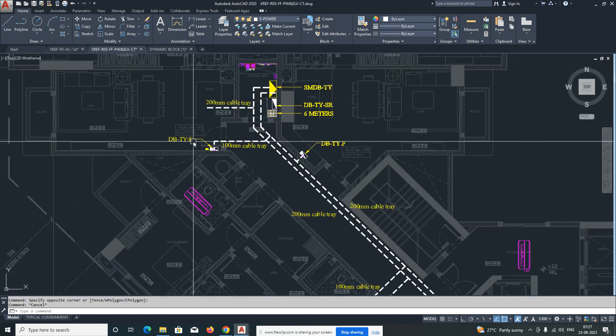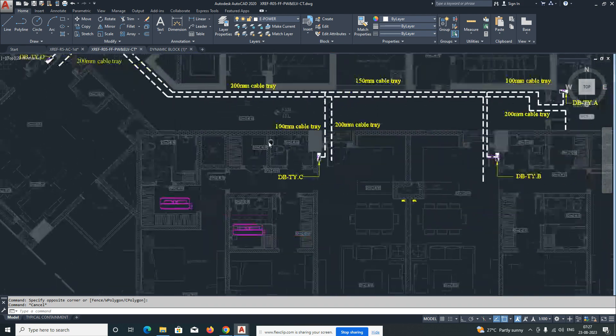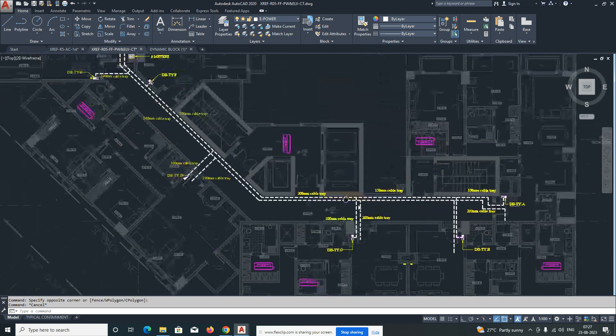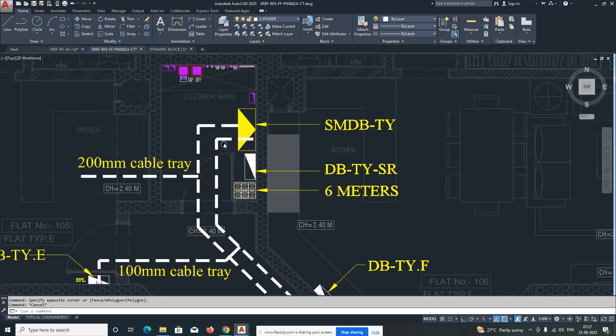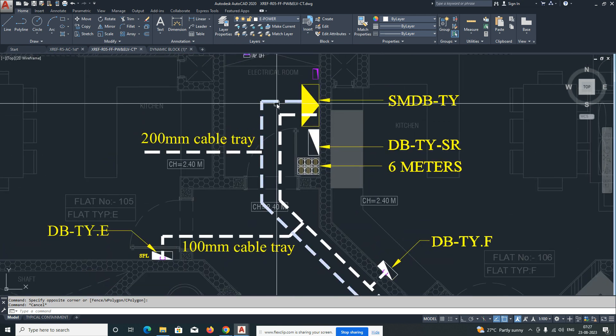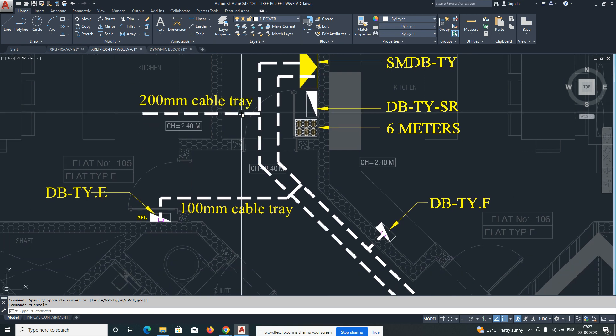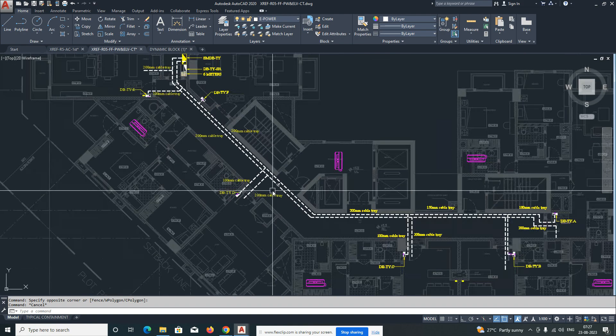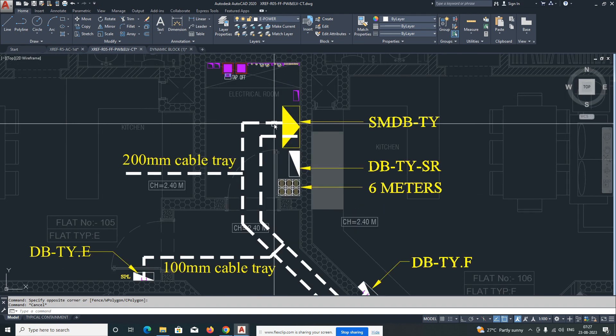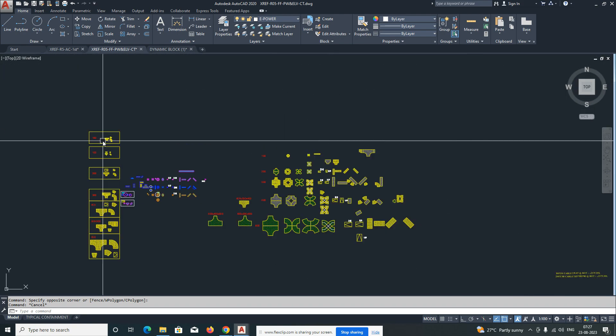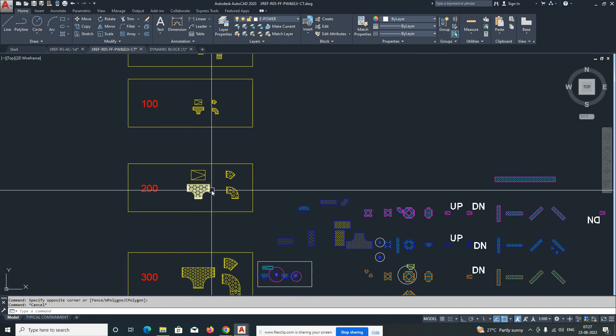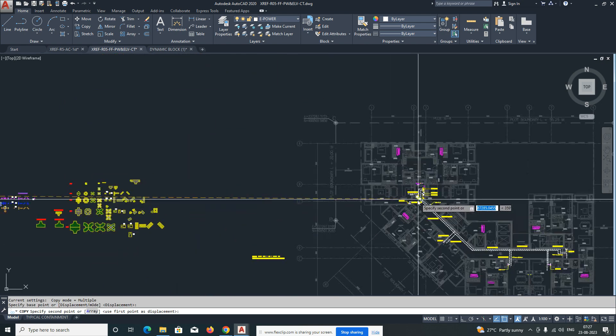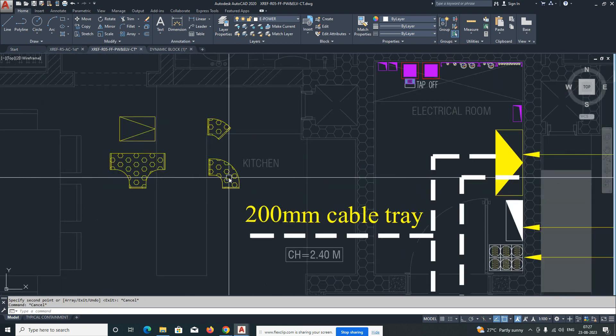The DBs are already placed in each apartment — they have provided each DB. We need to distribute the power for that. This is the design drawing and we need to develop the shop drawing. This is 200mm cable tray, 100mm cable tray, and it's divided like that. We'll go for the 200mm cable tray first — we already made a dynamic block for that. We'll copy that one.